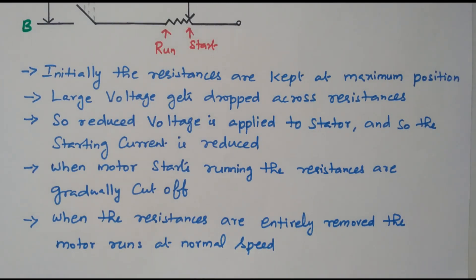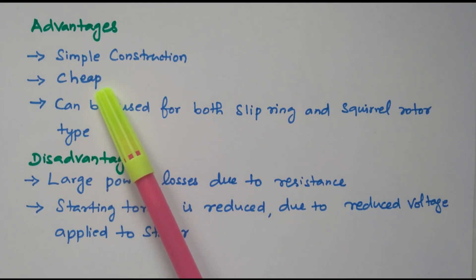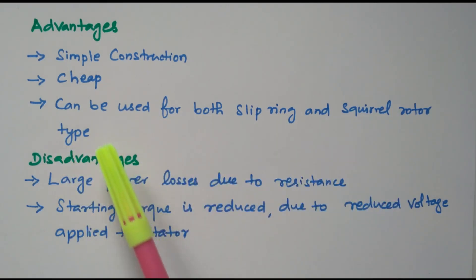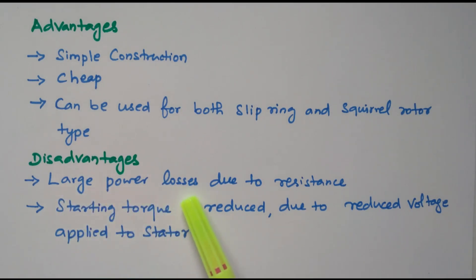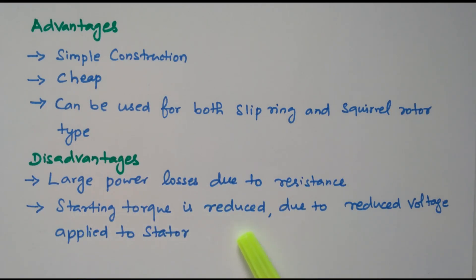Now we will see the advantages and disadvantages of the stator resistance method. The advantages are: it is a simple construction — only 3 sets of resistors are needed — and the cost is very cheap. The resistors can be used for both slip ring as well as squirrel cage types of induction motor. The disadvantages are: large power is lost in the resistors, because initially the maximum resistance position is used and the entire voltage is dropped across the resistor, causing more power loss. Also, the starting torque is reduced because only a reduced voltage is applied to the stator.